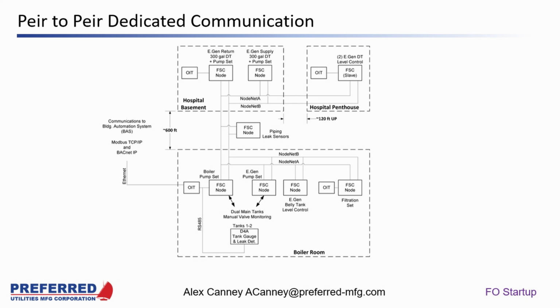I'm not sure if it was covered in the webinar, but that pump, that FSC system, could still be run. It just wouldn't be able to be run from the central controller, correct Alex? Yeah, it depends on where the break is. Communication will still happen within that loop, but it depends on between which points the break happens. So there is a possibility for partial operation between sections.